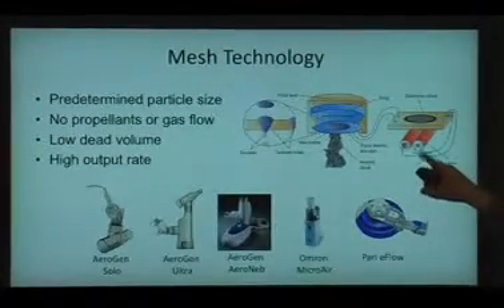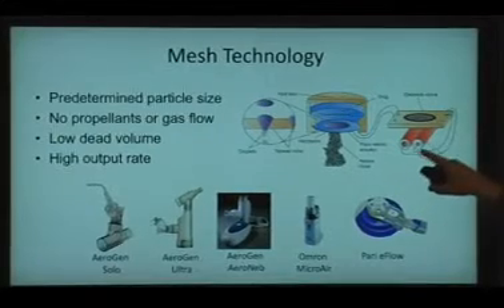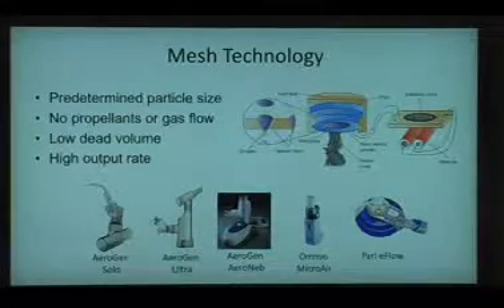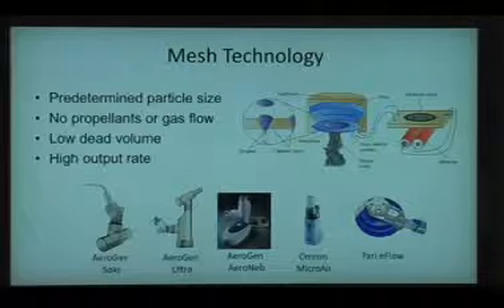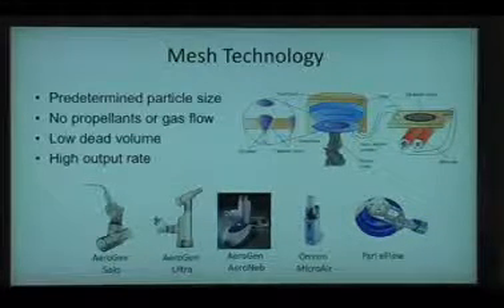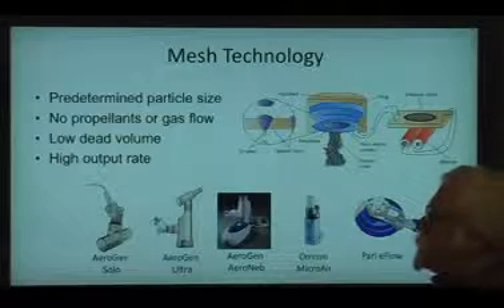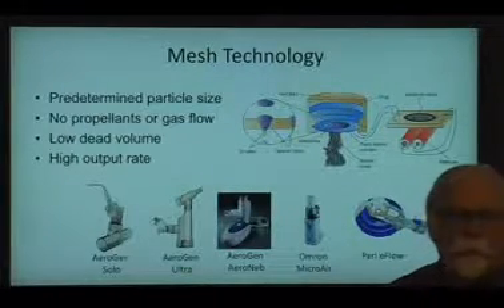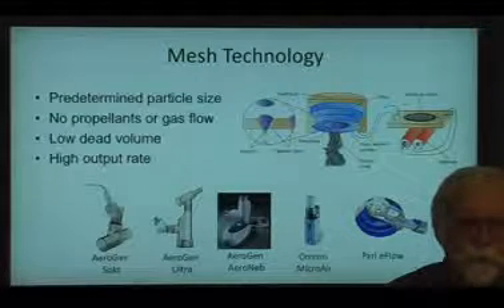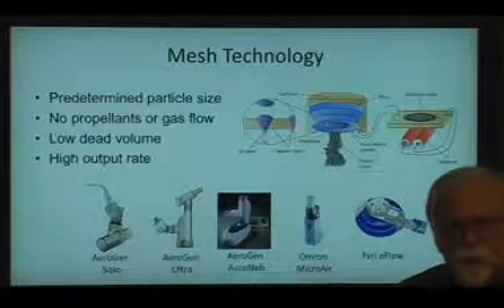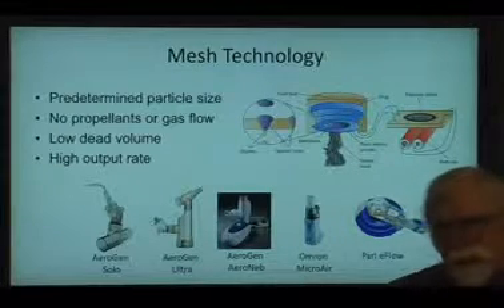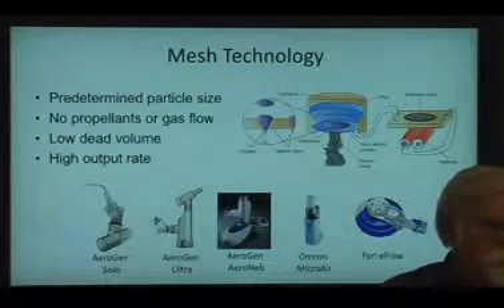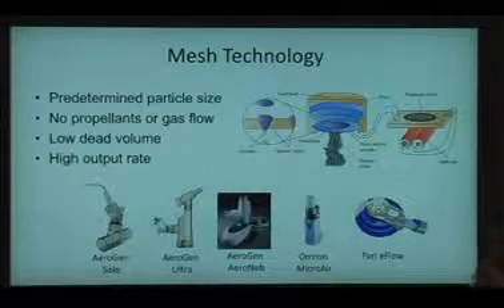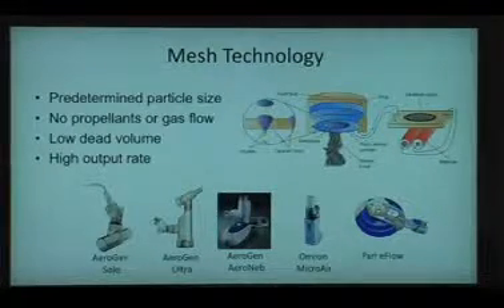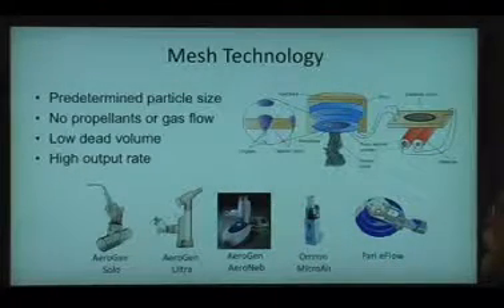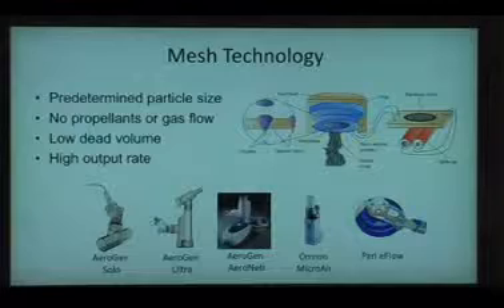So some of these are specifically designed for a specific formulation of drug. These use no propellants or gas flow, so that's an advantage. They have virtually no dead volume if they operate correctly. So that's an advantage over a jet nebulizer. So the way that the mesh nebulizer is supposed to work is you put the solution in, and all of the solution is aerosolized to complete dryness inside of the device. Now, as I'll show you some data in a minute, that doesn't always happen. And it has a high output rate, so it doesn't take long to deliver the drug.